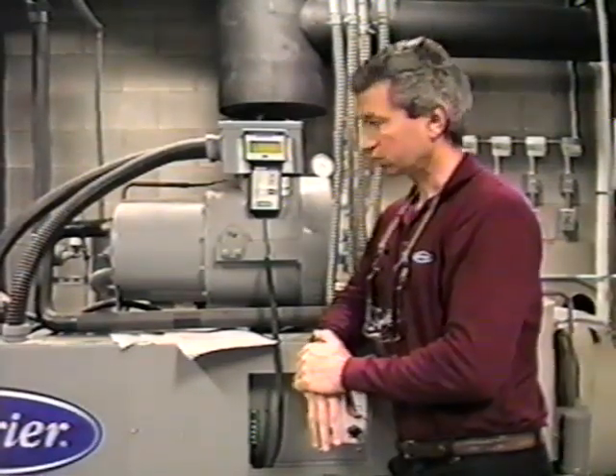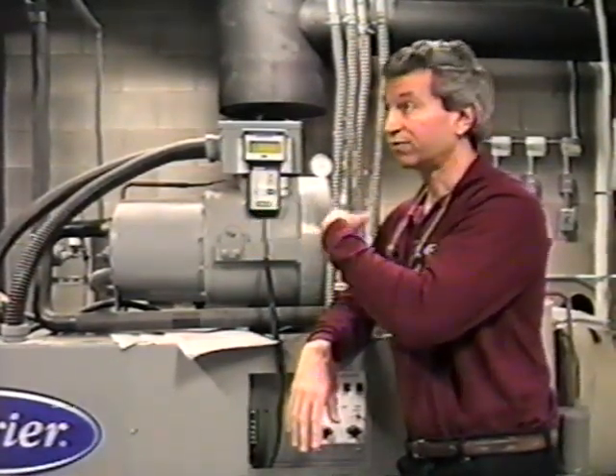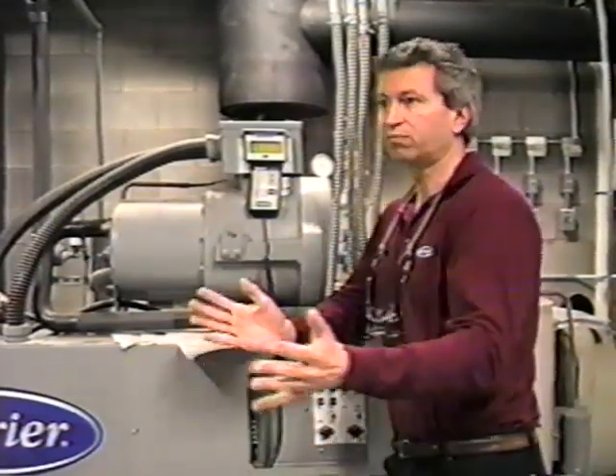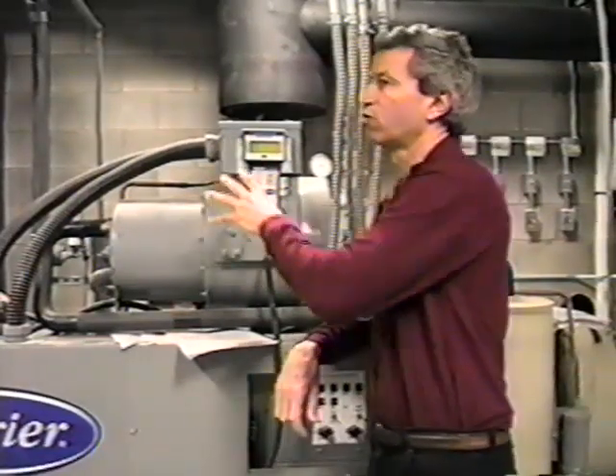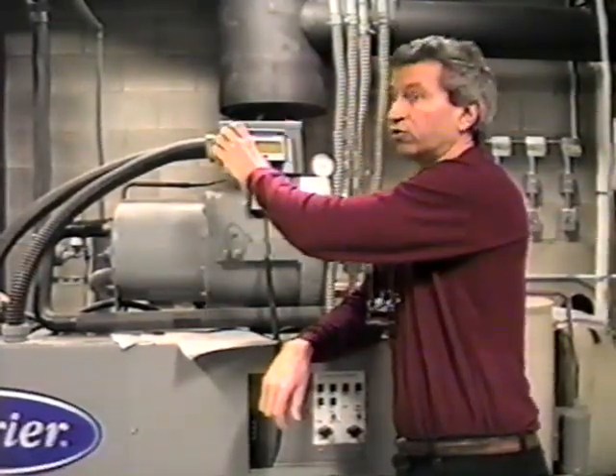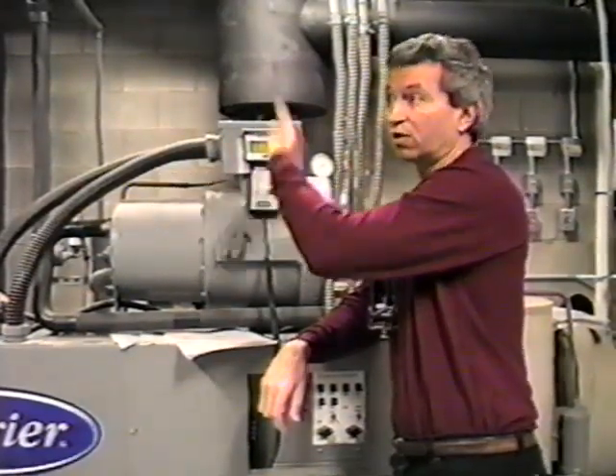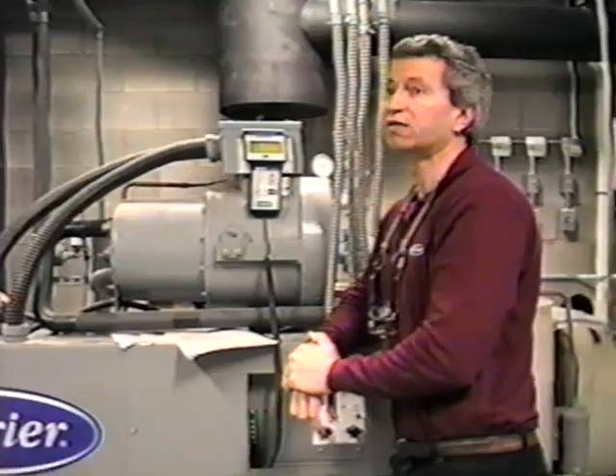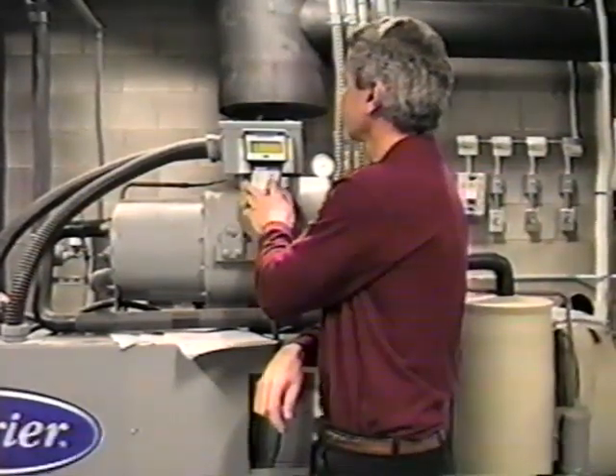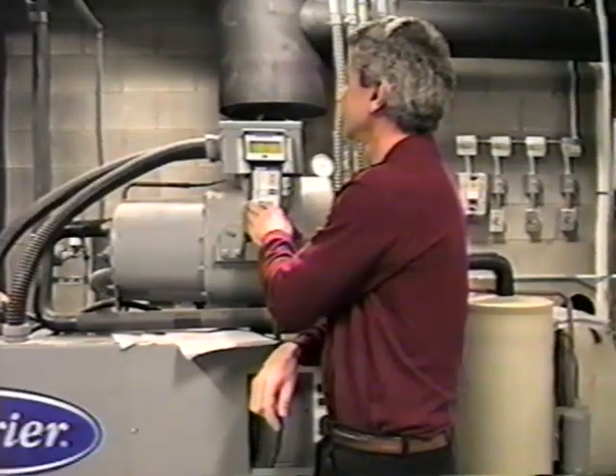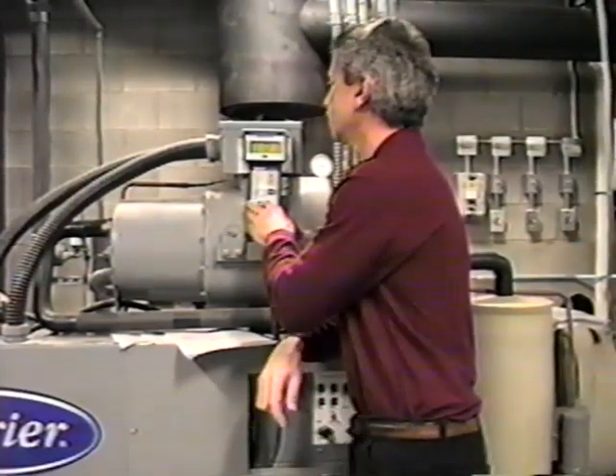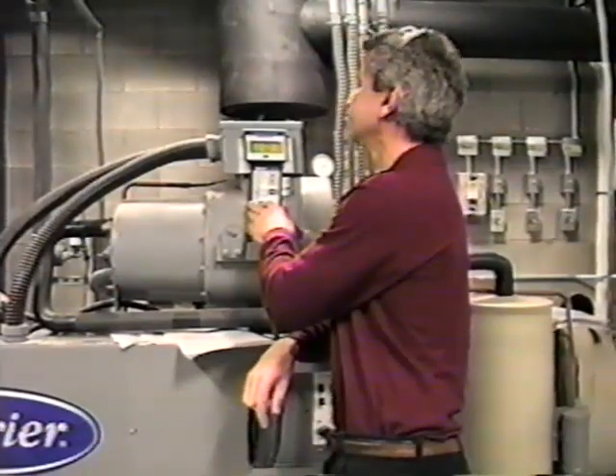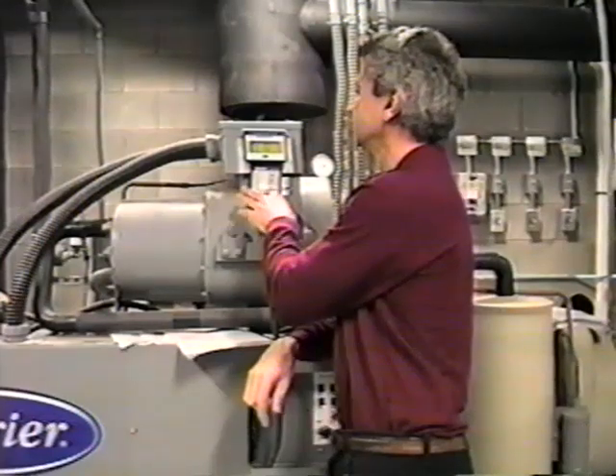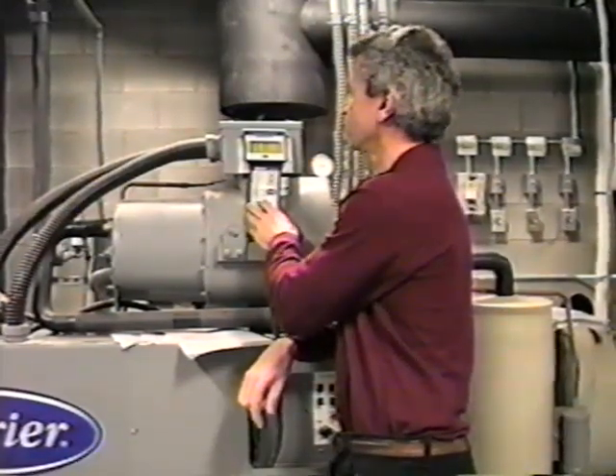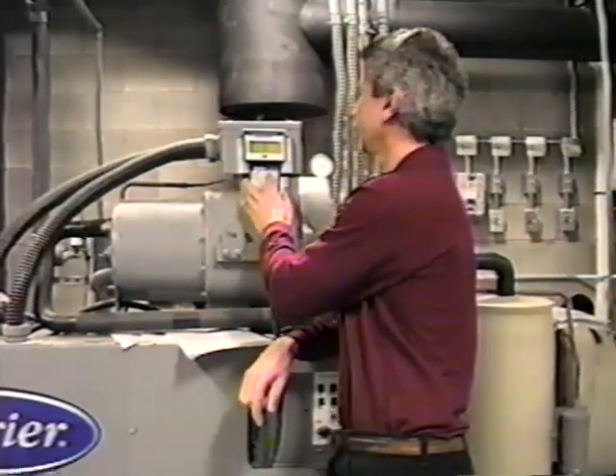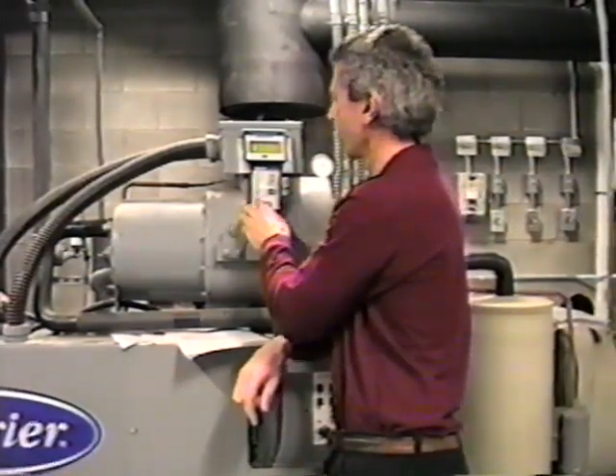Okay. But there is a place for a schedule, and you could even set the schedule. But again, if it's not programmed to look at it, it doesn't matter. If you were programmed to look at the schedule, that screen will tell you that you're in a time occupied mode or an unoccupied mode, that you are being controlled by that time schedule. Okay, time and date, and again, that's where you set up your month of the year and the day of the month. Okay, so that's all been done. And then schedule. Again, that's where you set your occupied and unoccupied if you're going to operate under a schedule.